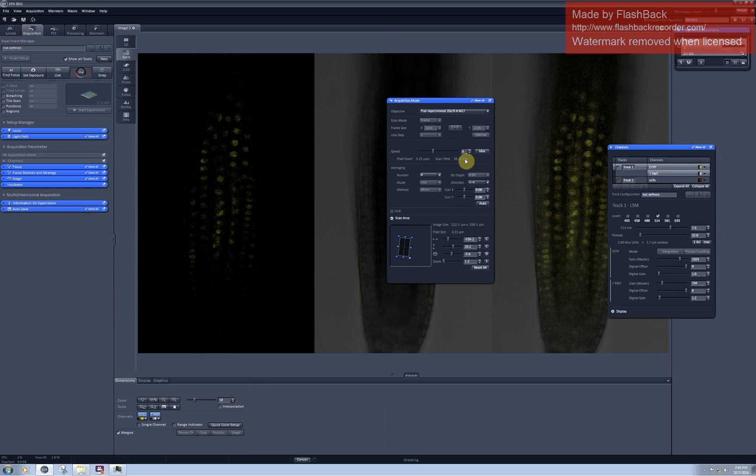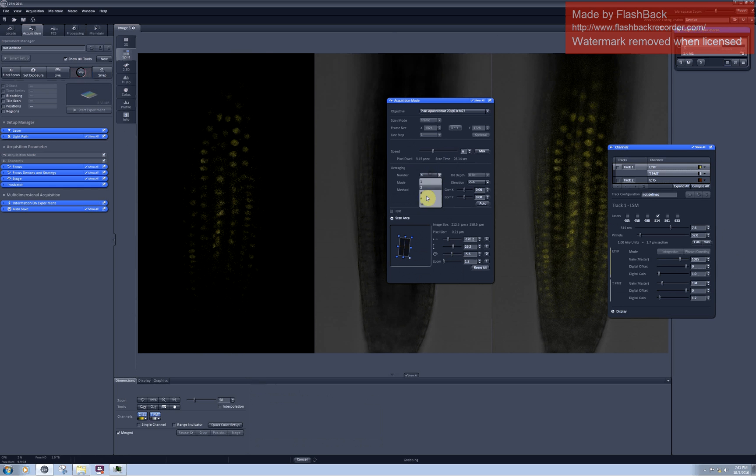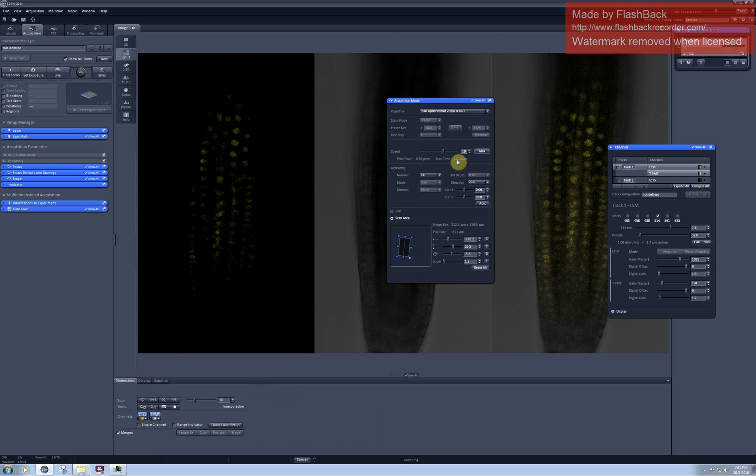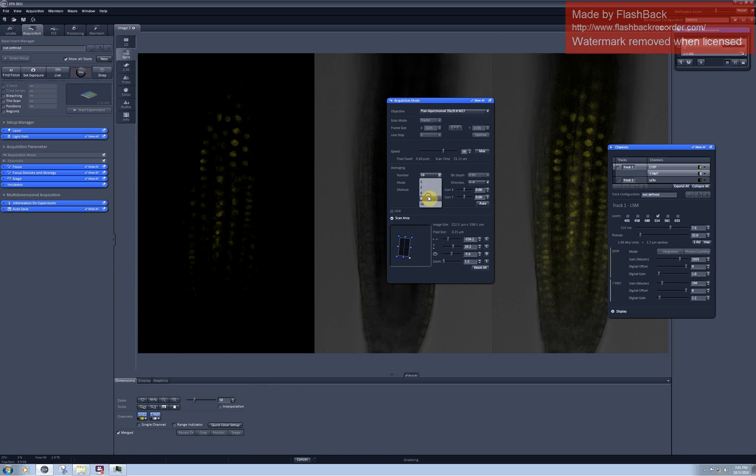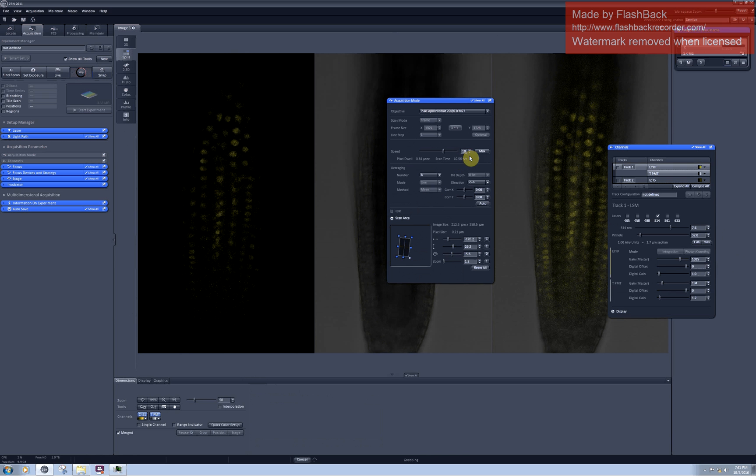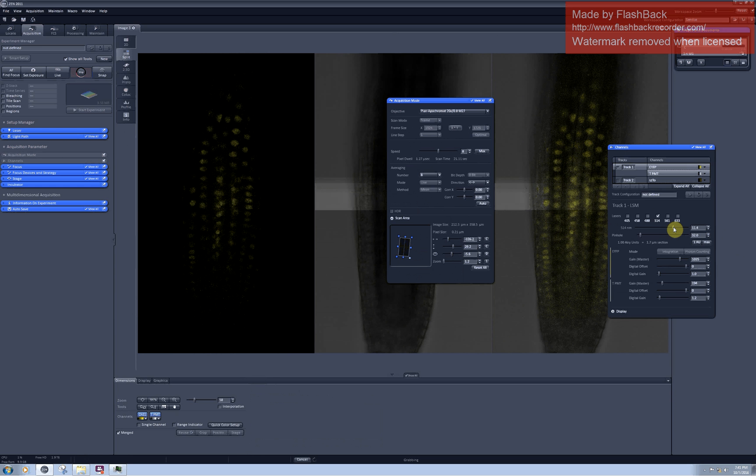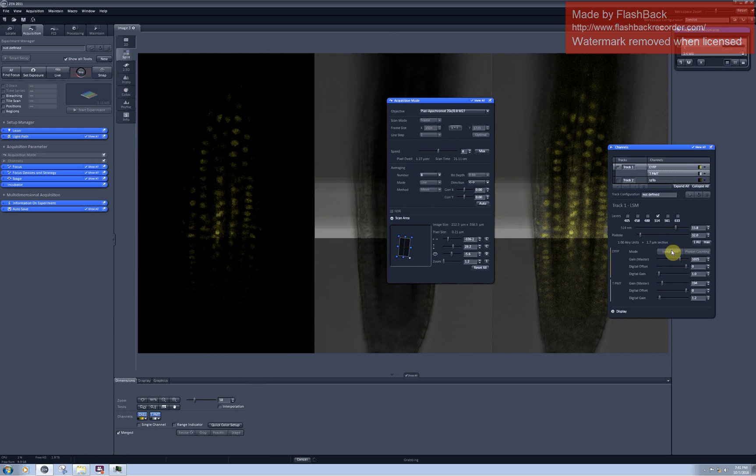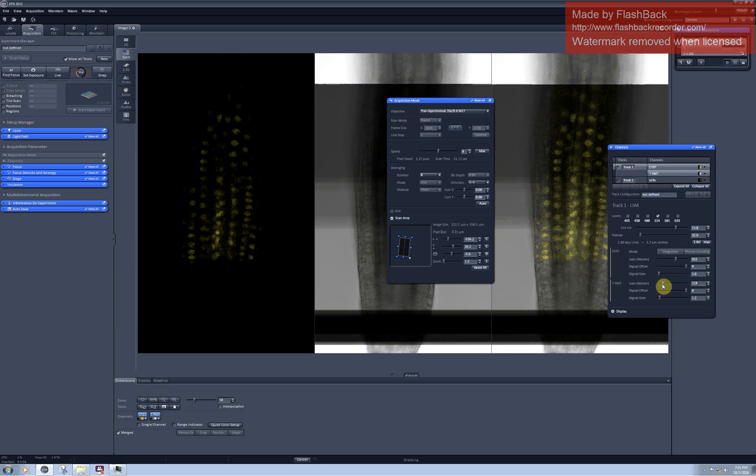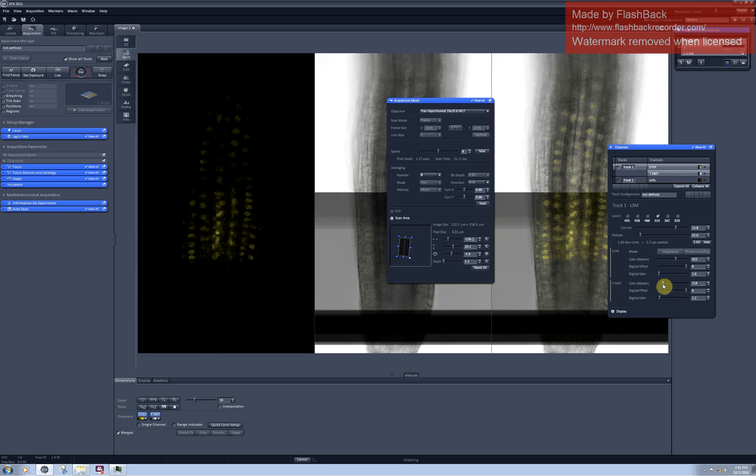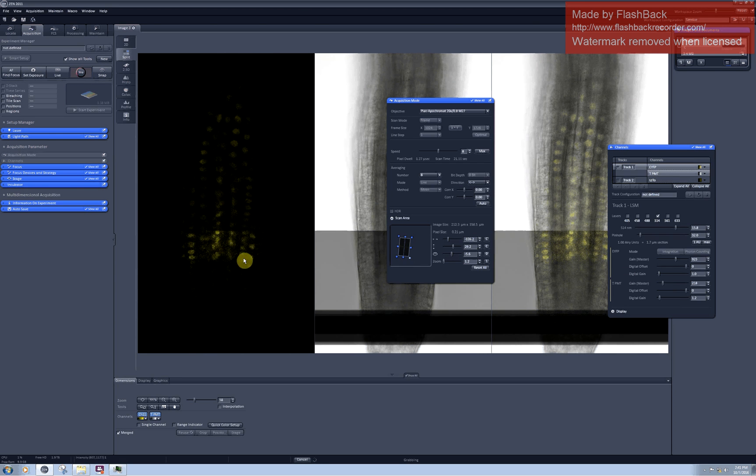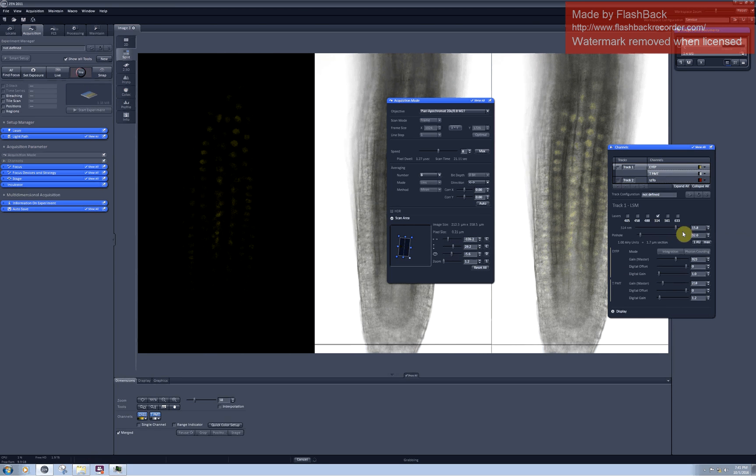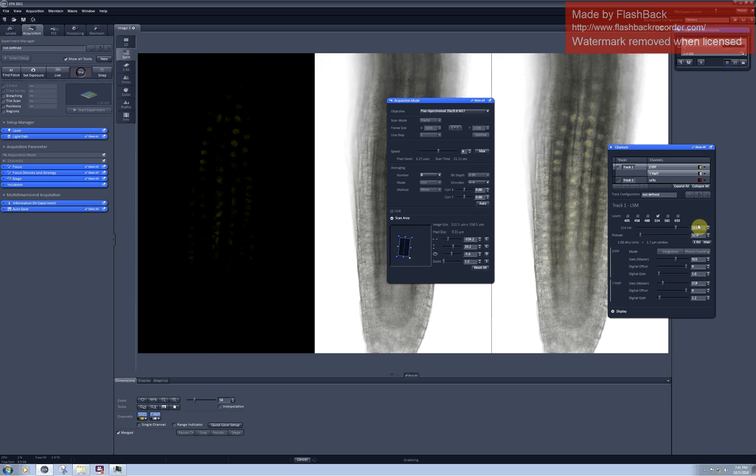And now it takes 26 seconds. How about this combination? Not much faster and not much better. How about this one? Much more pixelated. I could increase a little bit more the laser intensity and pull a little bit more the gain. This looks slightly better. But now I have quite high laser intensity which might lead to photobleaching and phototoxicity.